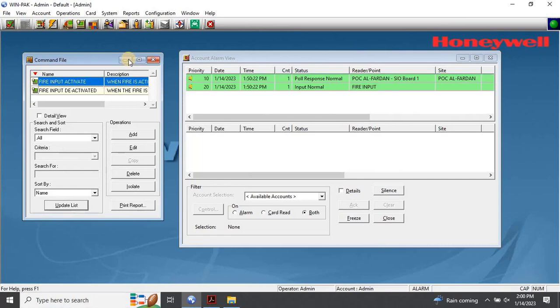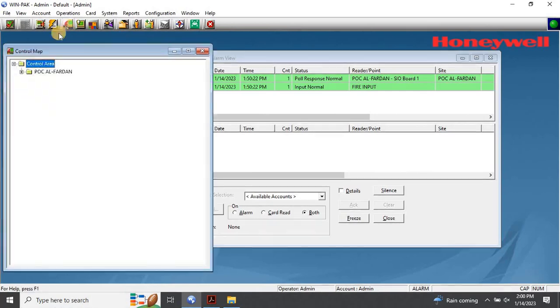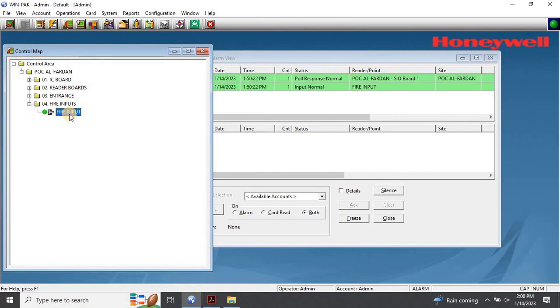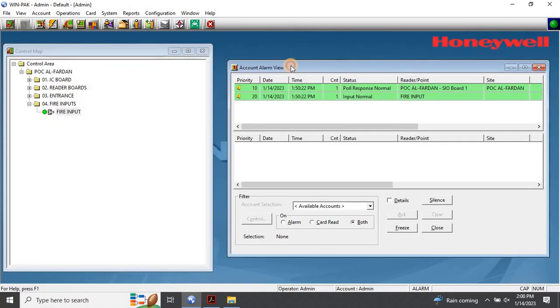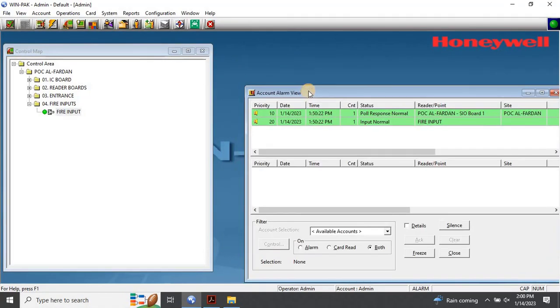Now let's find the device in the control map. The control map enables you to view and control the devices belonging to the control area. In addition, you can view the status, acknowledge and clear alarms, and run various commands for each device. To control devices from a control map, choose Operations, then Control Map. The control map window will appear. Expand the control area to view the details of its branches and devices. The status of each device is indicated by the color to the left of the device name. As you can see, our fire input is in a normal state.